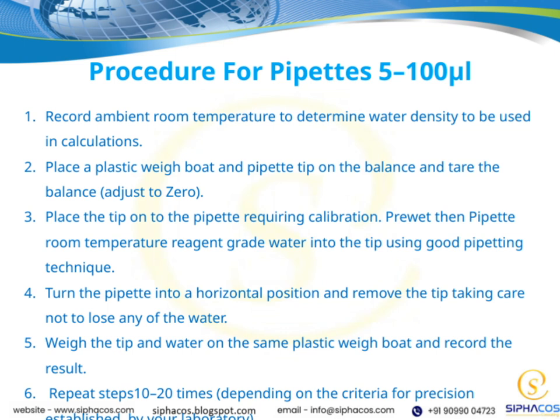Record this measurement accurately. Repeat these steps 10 to 20 times, or as many times as needed to meet your laboratory's precision criteria. This process helps ensure our pipette calibration is accurate by accounting for variations and verifying consistent volume delivery. Remember, the key points are maintaining good pipetting technique, accurately weighing, and recording multiple measurements to achieve reliable results.